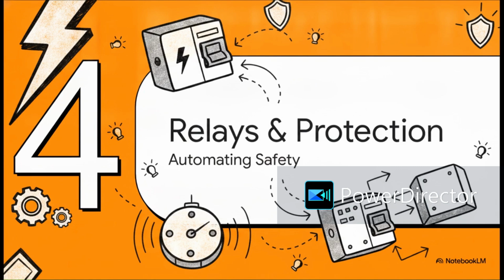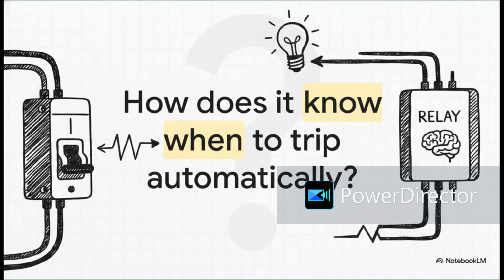Moving right along to part 4, relays and fault protection. So this begs a pretty big question. How does the breaker actually know when to trip automatically? Think about it. If no one is standing there to flip the switch, how on earth does it sense danger? Well, it's because circuit breakers never really work alone. They're paired up with these things called relays.